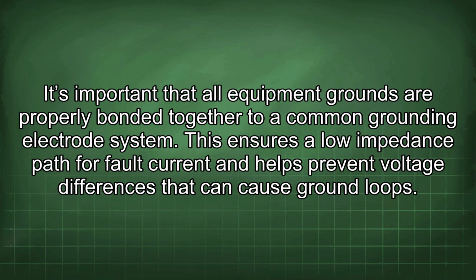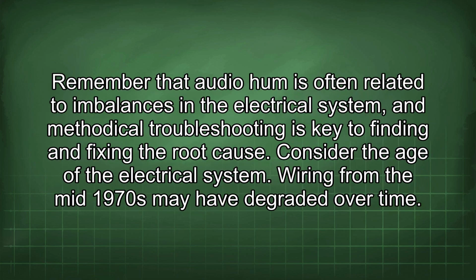It's important that all equipment grounds are properly bonded together to a common grounding electrode system. This ensures a low impedance path for fault current and helps prevent voltage differences that can cause ground loops. Remember that audio hum is often related to imbalances in the electrical system, and methodical troubleshooting is key to finding and fixing the root cause.